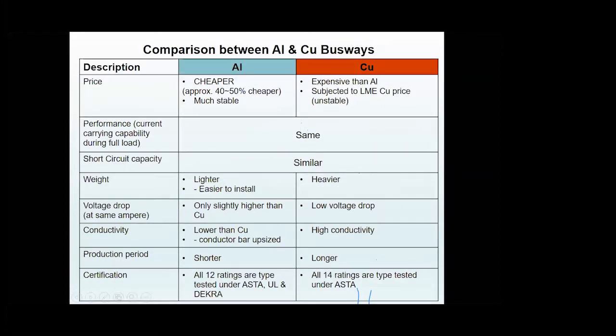Just like cables, busway also comes in aluminum conductors and copper conductors. The biggest difference is price — aluminum is about 40 to 50 percent cheaper than copper, and aluminum prices are more stable compared with copper, which follows the LME copper price that fluctuates every day. In terms of performance, aluminum and copper busway are essentially the same. In terms of conductivity, aluminum is lower than copper, so we upsize the conductor bar — aluminum will be one size bigger to cater for the same performance.